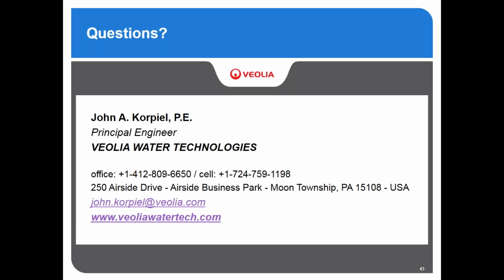What are the temperature limits for the RO membranes? Well, the Aura membranes we use in OPUS, there's nothing special about them. They're just standard thin film composite seawater RO membranes. And the warranty limit is generally 113 Fahrenheit, which is 45 Celsius. We generally run them as high as 40 Celsius or 105 Fahrenheit. As you may have seen on that slide that I showed of the California installation, we use a heat exchanger to regulate the temperature to around 38 or 40 degrees Celsius. The hotter the temperature, you enjoy lower pressure, but the hotter the temperature, you also get higher salt passage. So there's a balance there.